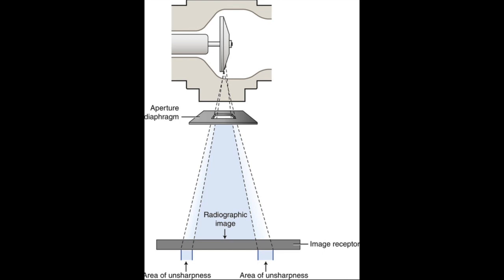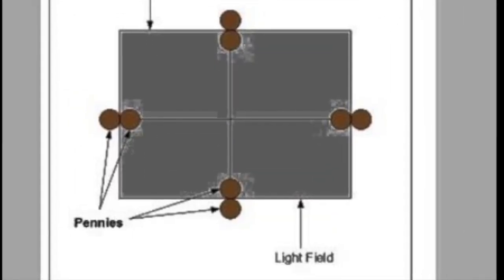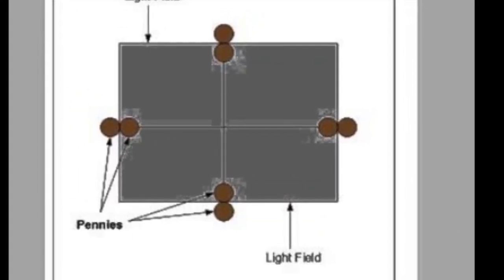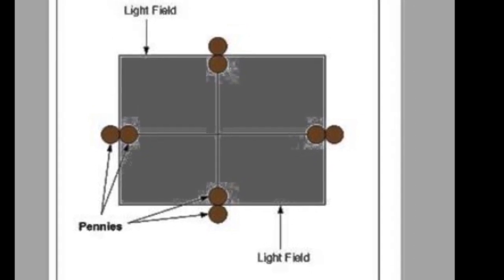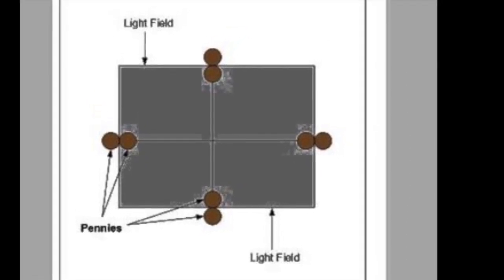These factors may be tested simply using a tape measure and visual tests using congruence and perpendicularity tools to test the accuracy of the beam alignment with respect to the integrity of direction of the beam and accuracy of the collimated field. The example shown is an example of a penny test to check for light field alignment.